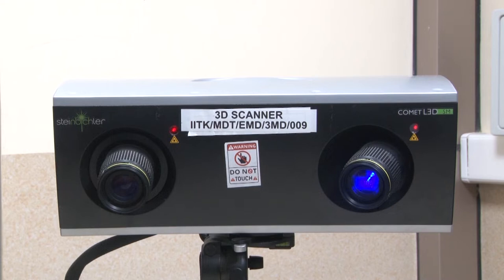This is the scanner machine, the German-based Steinbichler Comet L3D 5M. There were two versions available when this was purchased, 3M and 5M. Now we have multiple other versions. 5M means 5 megapixel, that means it can record 5 million points per second. Majorly it has two lenses. One is a camera, which is a 60 frames per second data capture camera.